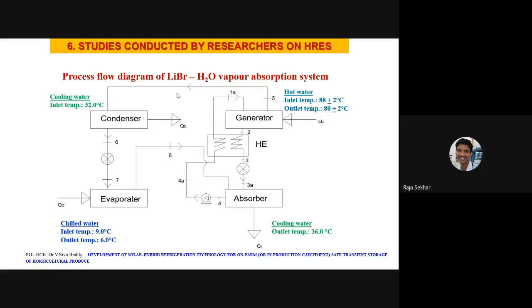But with this, one of the challenges is that you have to maintain a vacuum. Vacuum here does not mean 100% vacuum; a vacuum of up to 20% should be maintained for operation. These are the corresponding operating parameters. At the generator, the inlet temperature of water is 88 degrees, and after the heat exchange the outlet temperature was 80 degrees. That means there is an 8 degree drop in the hot water temperature.